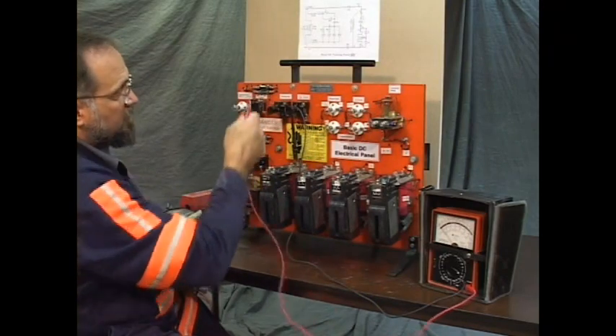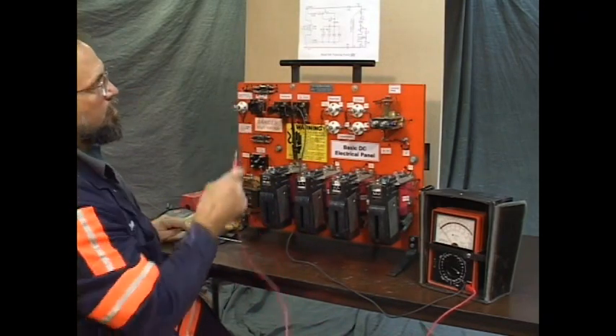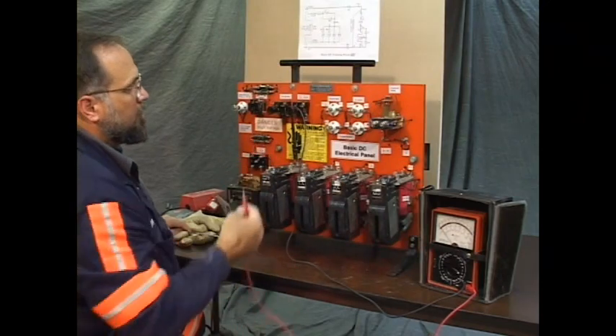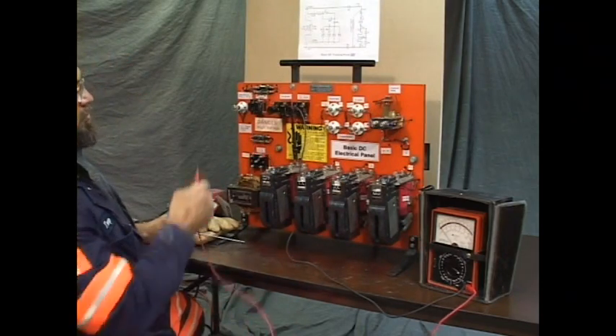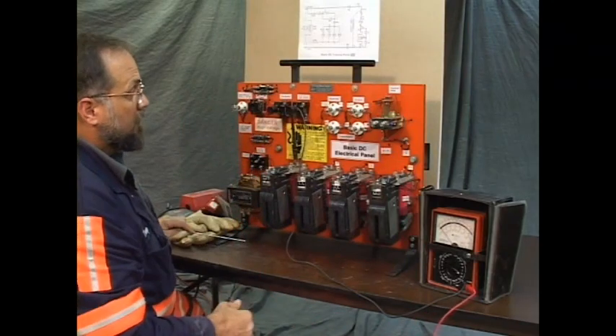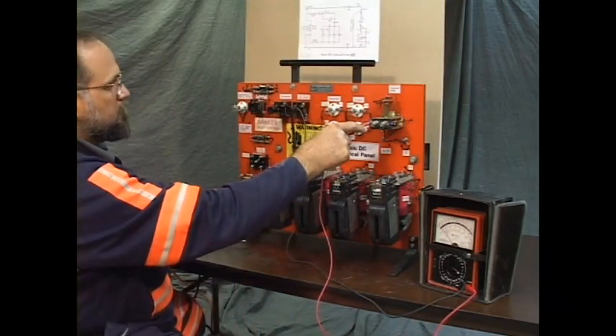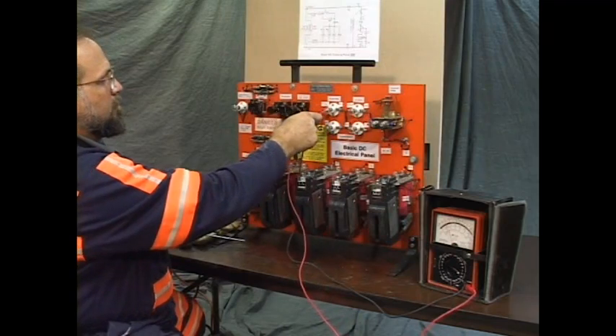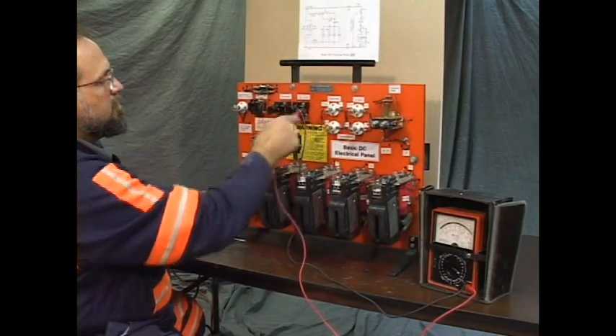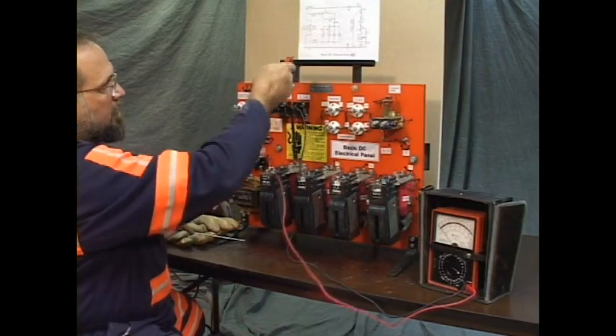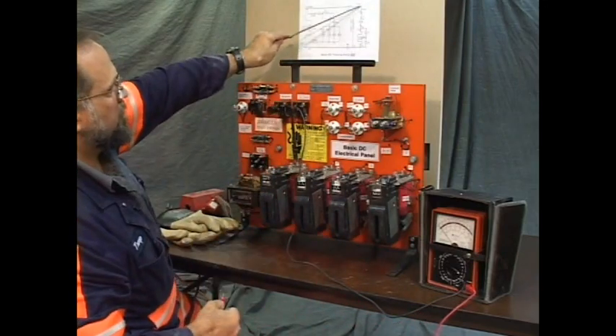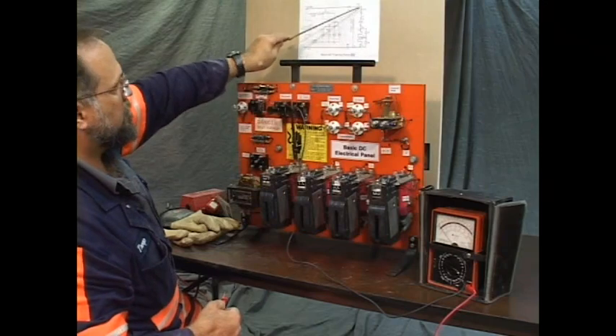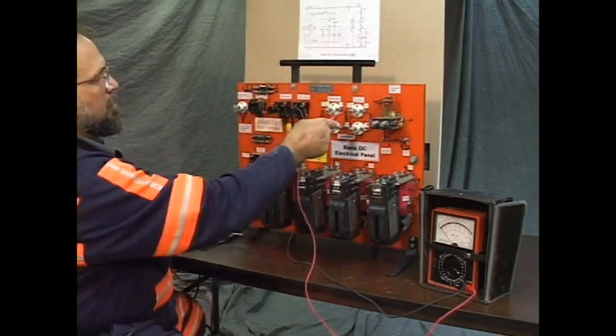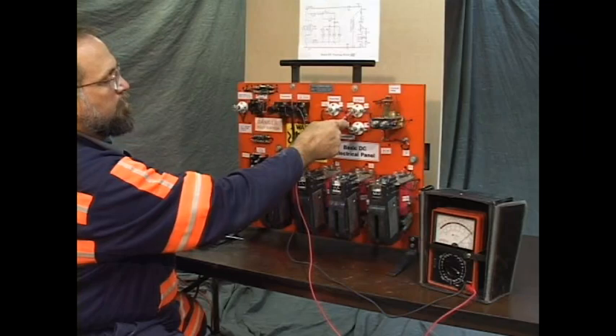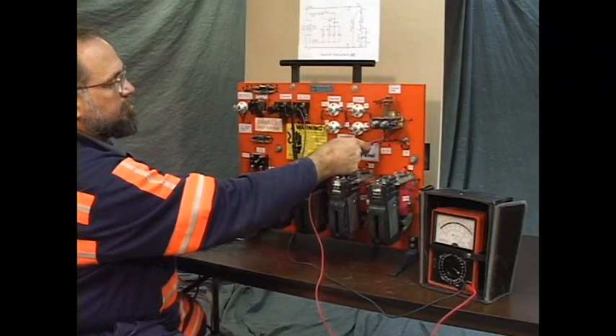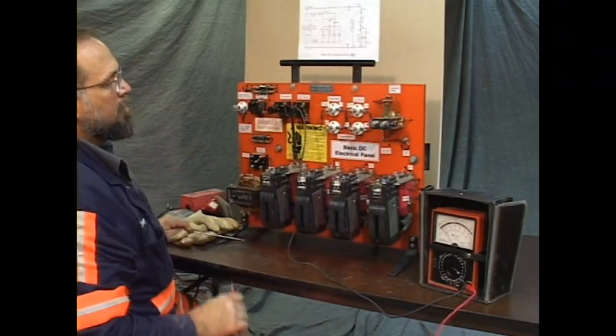Now, this is the beginning of the parallel circuit in the motor. You can take one line or the other. Routinely, I take the shunt field because it's the first one I come to. From the shunt field, F2, S2. It's good. I can also take S1A1 from this point right here, that's here, and right there to there. That's here. There's a post on this panel for your convenience to check to. And there you have it.